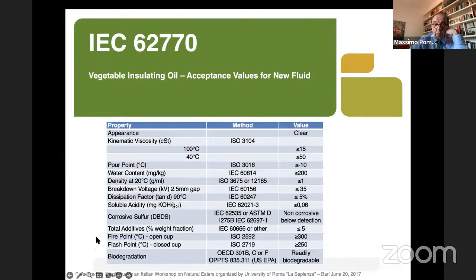Then we have pour point. Pour point is the temperature related to very low temperature. Is the limit at which you can still use the liquid, because otherwise the liquid, especially the oil, started to become similar to wax, so is no more able to circulate in transformer. Then is a maximum for water content, is some limit for density, so breakdown voltage.